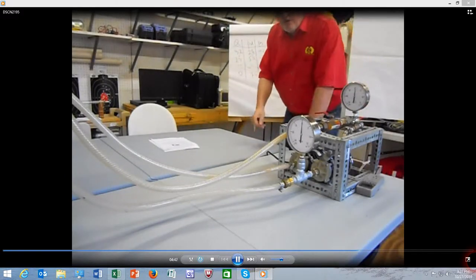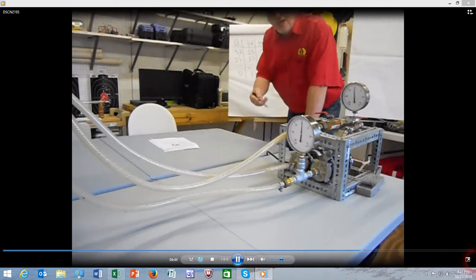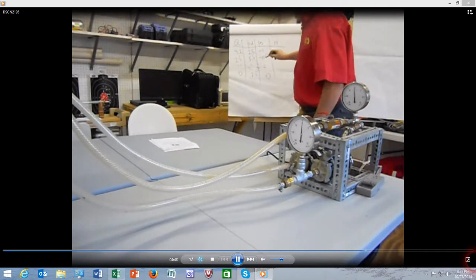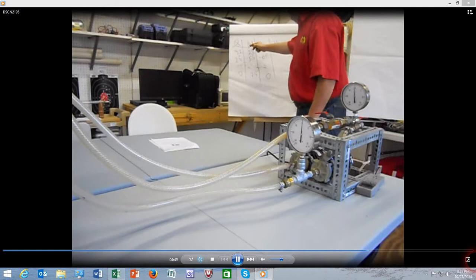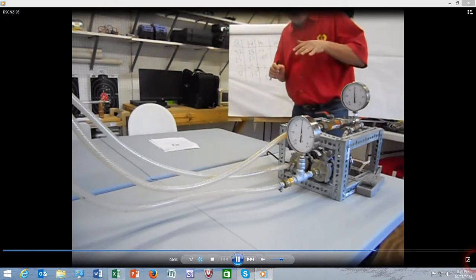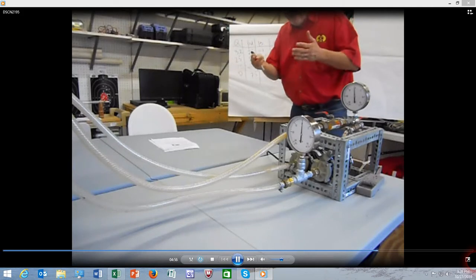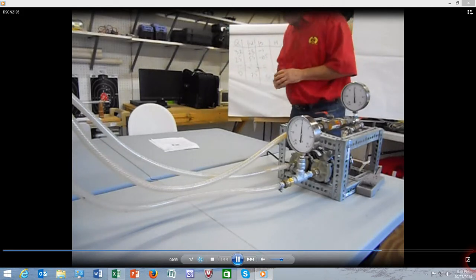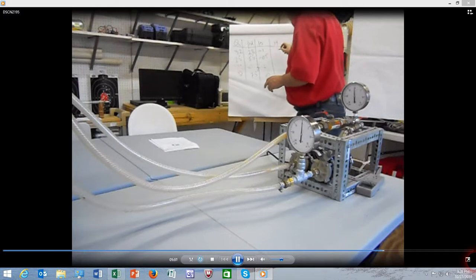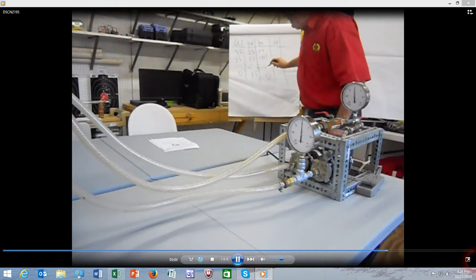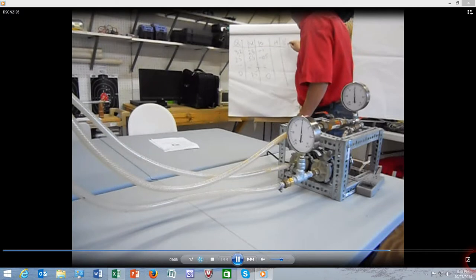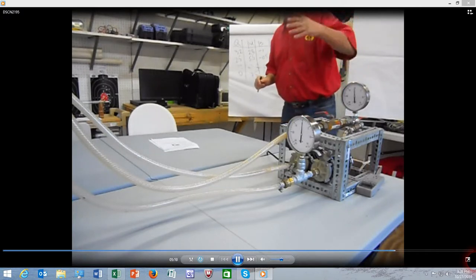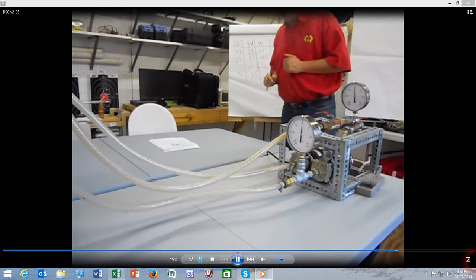Now, of course, to calculate pump head, pump H, we have to take differential between discharge and suction pressure times 2.31 in U.S. units, divided by the specific gravity. I did 1.0 specific gravity for water in this test. And then we'll get calculations of pump head. And then in every point, we'll calculate specific speed of the pump for the formula we just discussed, along every point.